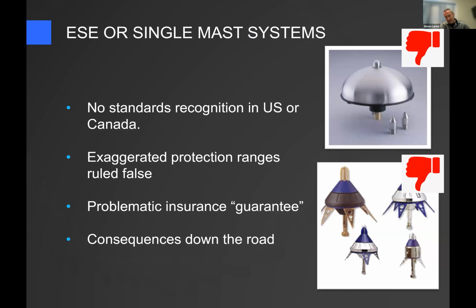Remember I talked about the counter leader coming up from edges, corners, lightning rods, tops of trees, whatever. Lots of places for ion channels to start that upward counter leader. The ESE device people say their device helps emit a counter leader sooner, that moves faster up to connect to the downward stepped leader earlier. So it protects like an umbrella because it connects to that stepped leader sooner and higher up, it protects a wider area. In fact, I saw one of the manufacturers claim something like a 200-something meter protection radius for their device on one of their submittal drawings. That's absolutely impossible. There is just no way.